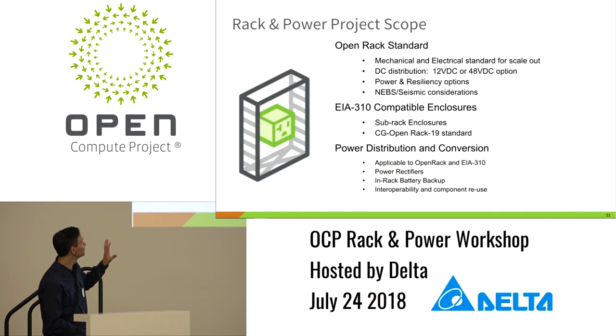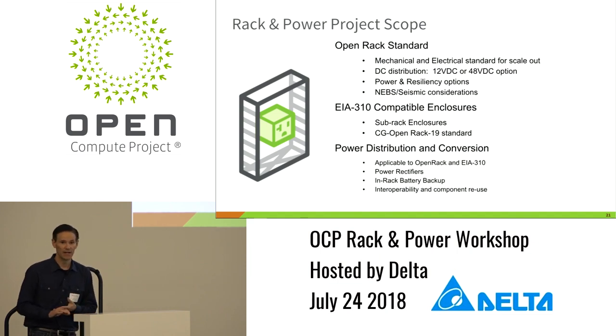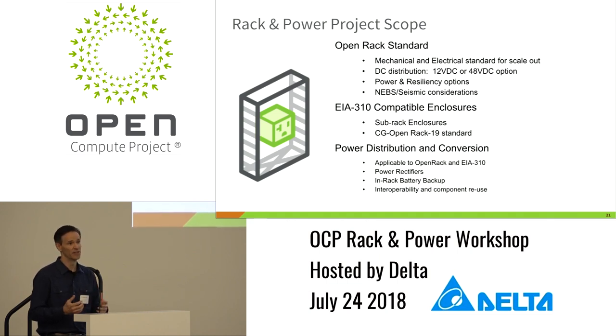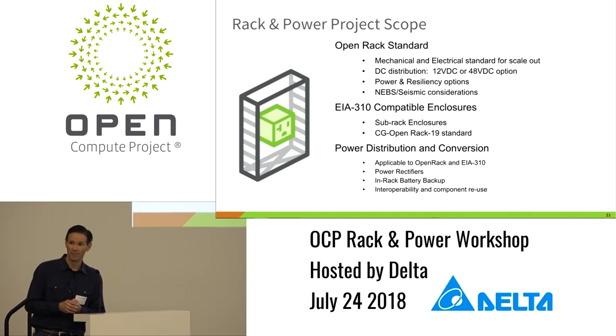This is the scope of Rack and Power. It has specifications that define both mechanical as well as electrical requirements for both 12-volt and 48-volt infrastructures. There's not a lot of detail defining the height of the rack, the depth of the rack, or the power shelves — no restrictions on how big the power shelves are or the type of technologies used. It defines those interfaces though: whatever you're generating at 12 volts going onto the bus bar, what are the conditions for that power once it gets there? That gives the community a lot of opportunity to innovate around what that power shelf is while still making sure all the IT gear plugging into the bus bar is compatible.